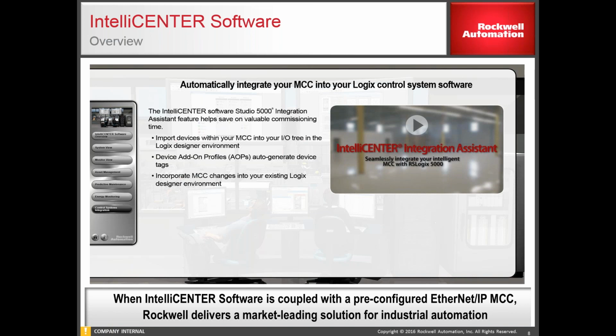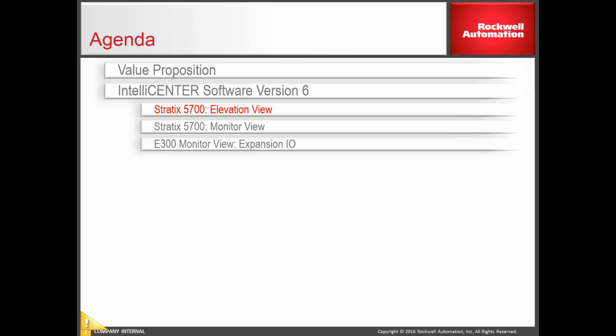So I know if you have a power monitor set up on the MCC, you can use a power monitor to look at the entire MCC. But I think for the IntelliCENTER software, you're going to be looking at the individual devices within the MCC. But with power monitor, you can certainly do that. And then the power monitor will trend that data as well, so you can go in and pull it out and look at it. If you have a fault condition or something like that, you can look at the data prior to the fault as well as shortly after the fault. Any more questions?